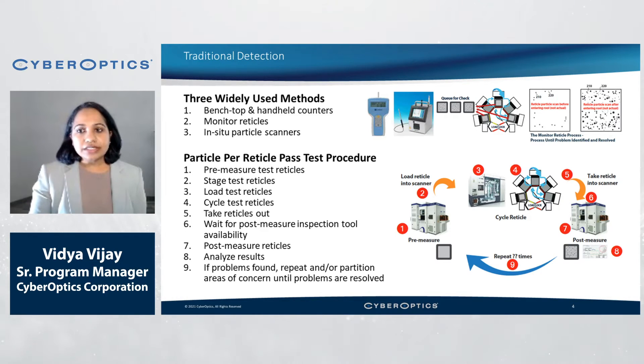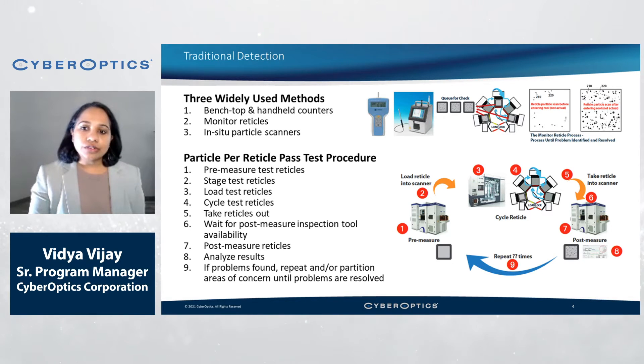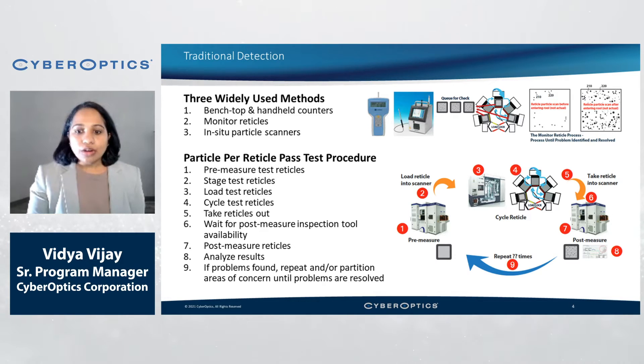Maximizing yield and tool uptime in photolithography environments requires best-in-class practices for a contamination-free process environment. Unfortunately, identifying precisely when and where airborne particles originate is challenging with traditional methods. There are three widely used methods for particle detection in photolithography environments: benchtop and handheld particle counters, monitor reticles, and in-situ particle scanners. All three of these traditional methods have substantial drawbacks.